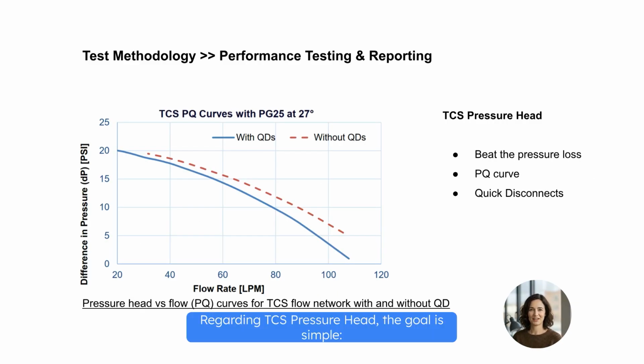Regarding TCS pressure head, the goal is simple. Your CDU pump must overcome the total loop impedance, the DP. You are calculating to beat the pressure loss. Look at the figure. This PQ curve shows available pressure versus flow. Notice the gap between the dashed and solid lines? That is the pressure penalty imposed by quick disconnects, QDs. You must factor this loss into your hydraulic budget.